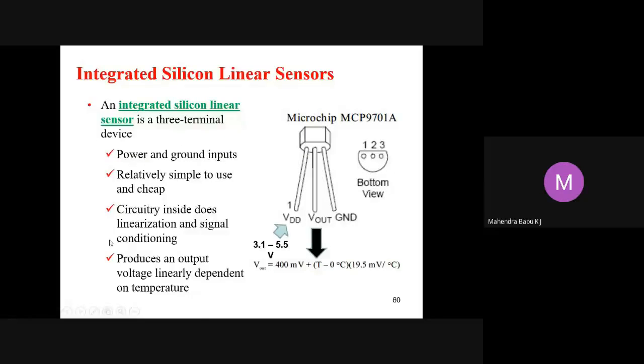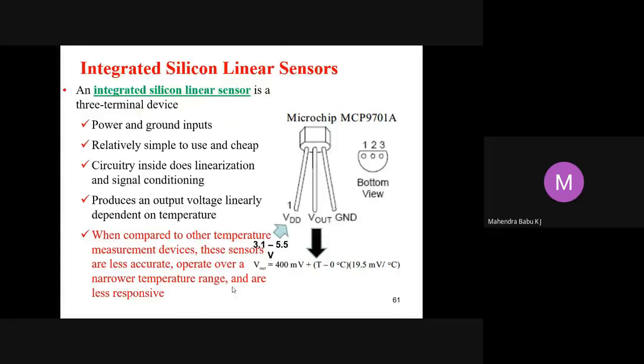Then we have integrated silicon linear sensors. An integrated silicon linear sensor is a three-terminal device which has power and ground inputs, and it is relatively simple to use and cheap. Circuitry inside does linearization and signal conditioning, and it produces an output voltage linearly dependent on temperature. When compared to other temperature measurement devices, these sensors are less accurate, operate over a narrow temperature range, and are less responsive.